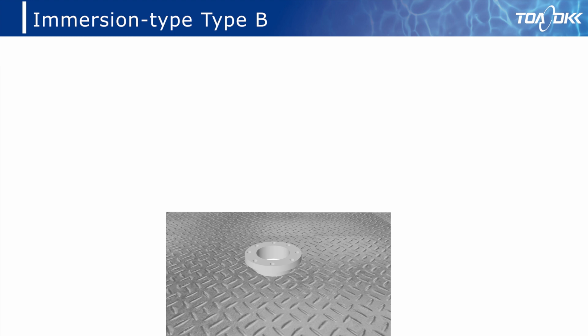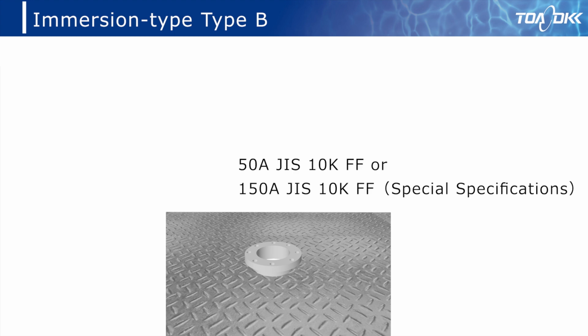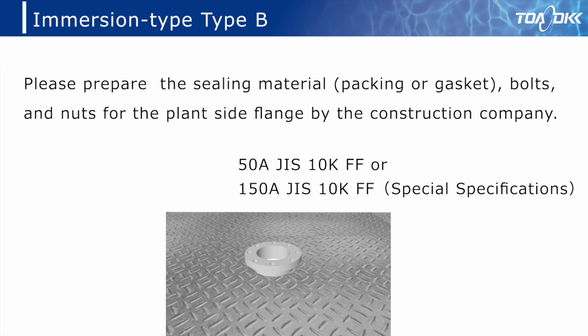The second specification is the immersion type vessel type B. This is installed on the flange at the upper part of the tank. Prepare the lower part of the flange and install it there. The flange standard is 50 A JIS 10K FF, flat face, flange mating. With the sealing material, packing or gasket, with the plant side flange, the screws and nuts, please prepare at the construction company.